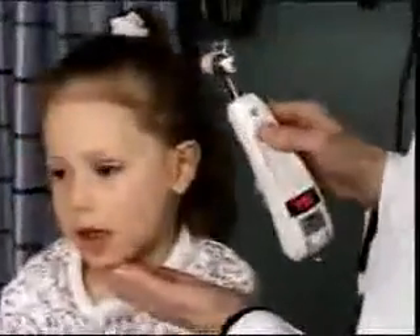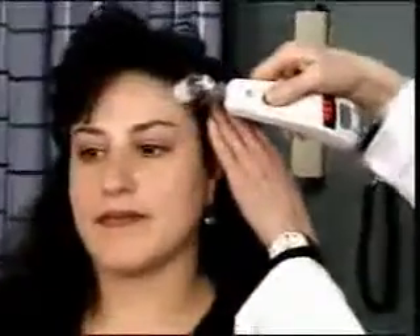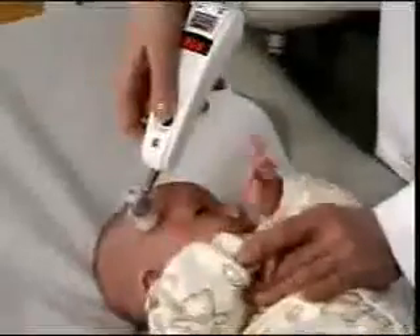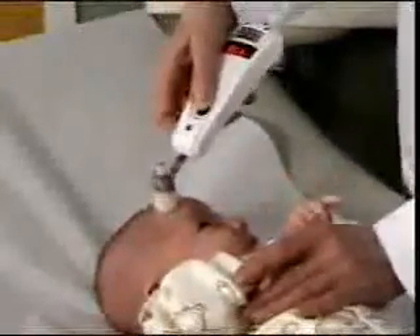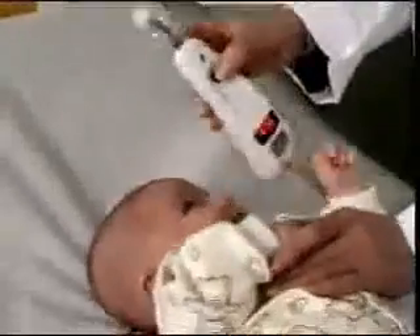You may wonder why we measure both the forehead and behind the ear. If the patient is diaphoretic, the moisture on the forehead will cause an evaporative cooling effect, leading to a measurement that is somewhat lower than the patient's actual temperature. However, the patient who is diaphoretic is always in a highly perfused state, which means the arteries are dilated behind the earlobe. To account for the heat loss in the forehead, we measure behind the ear. Why not measure behind the earlobe all the time? Because this measurement is too variable when vasodilatation is not present.